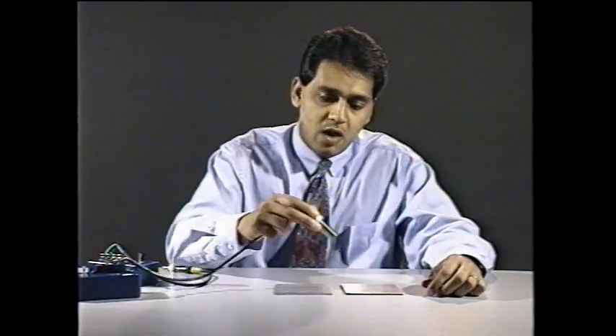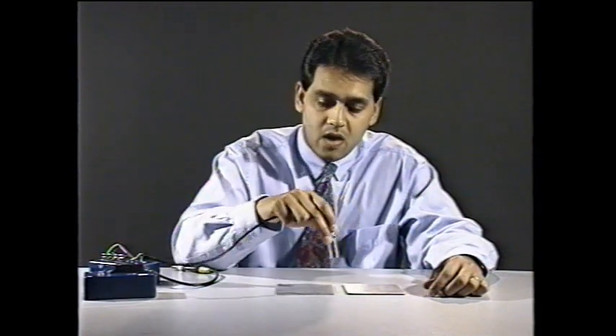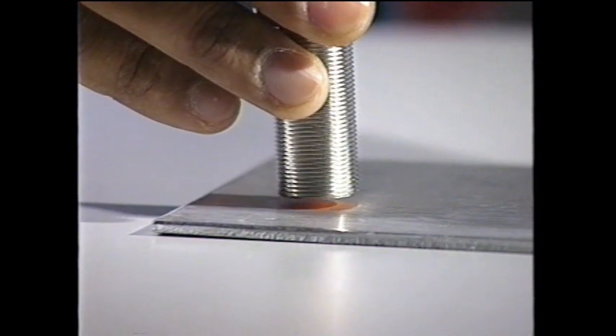The second point that affects the sensing range is the target material. So far, we've been using a piece of mild steel. Let's look at an aluminum target — same size, but just made out of aluminum. I'm going to use the 18-millimeter switch to illustrate the point. On mild steel, I'm getting five millimeters of range. On aluminum, you can see I'm getting considerably less range. The correction factor for aluminum is 0.4. Therefore, my working range is 0.4 times 5 millimeters. Anytime you're working with a material other than mild steel, always use a correction factor. The correction factors are listed in the training manual and also in the efector sensor catalog.